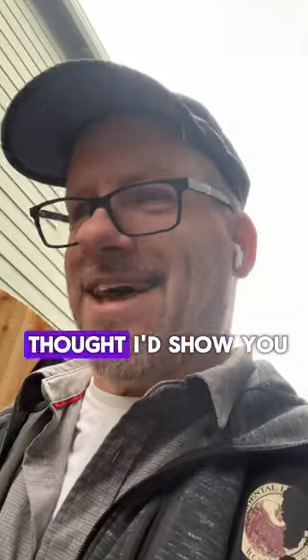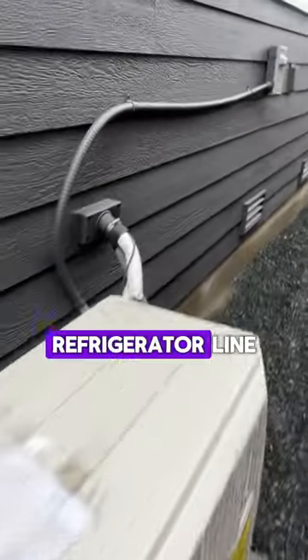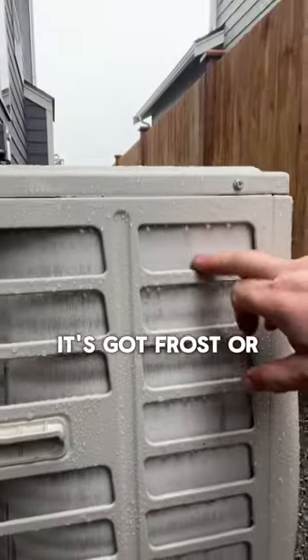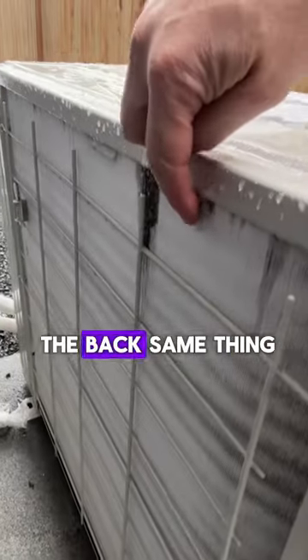I thought I'd show you a little video. This here, got a little heat pump system here. Refrigerator line, all that good stuff. But what's critical in this situation is, if you look in here, you can see how it's got frost or ice in here. You can see around the back, same thing.